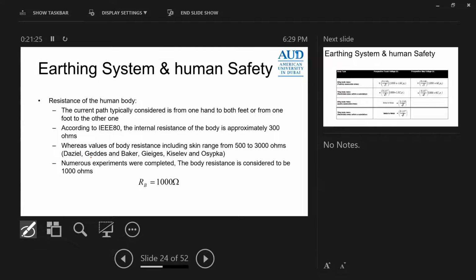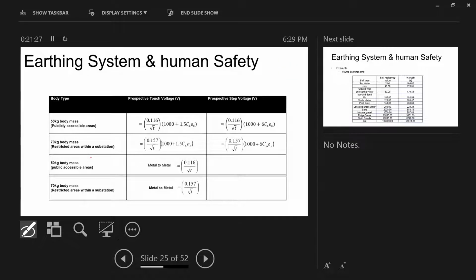Now, in this system, they consider the human body to be equal to 1000 ohm. What I want to show you now is 50 kilogram and 70 kilogram. These are the approved, the acceptable equations. T represents the clearance time. This rho S is the soil resistivity of your surface. This is the soil resistivity. That's your clearance time. And these are for a 50 kilogram and a 70 kilogram person.